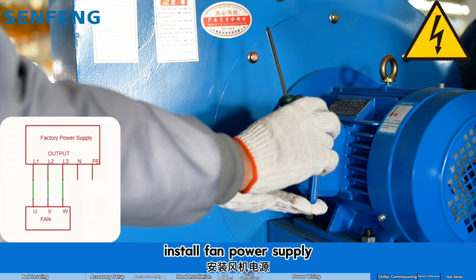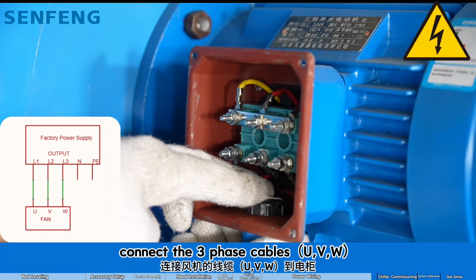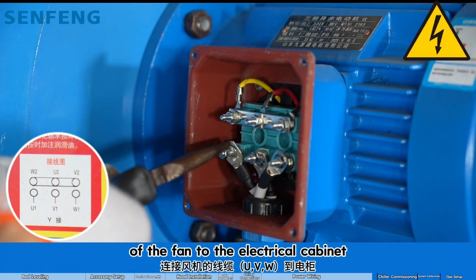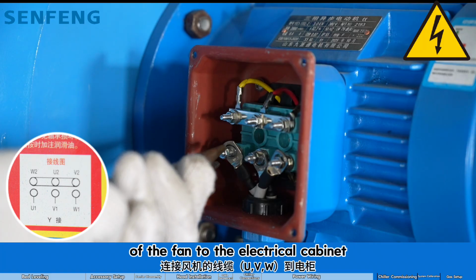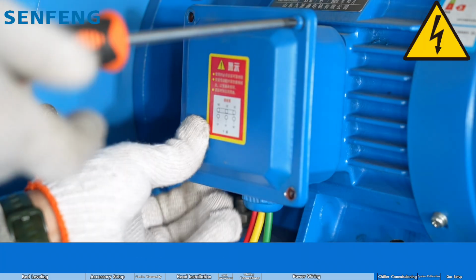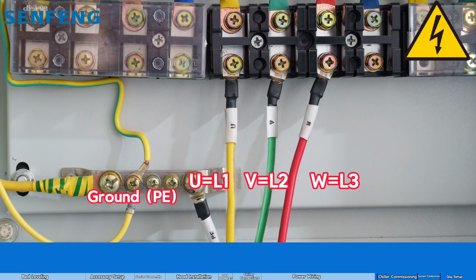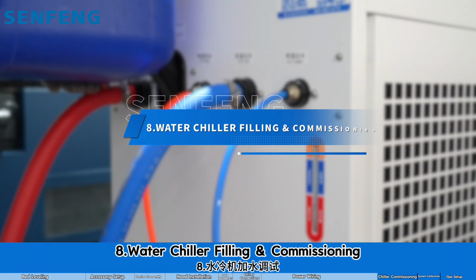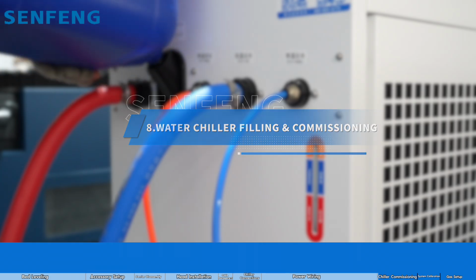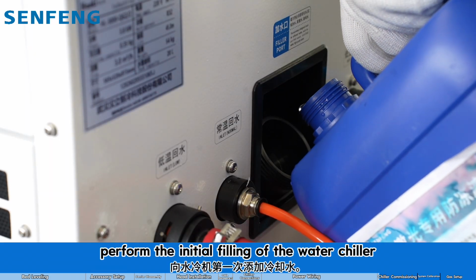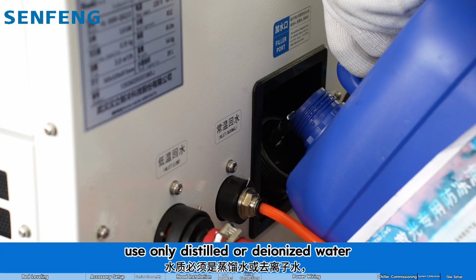Install fan power supply. Connect the 3-phase cables U, V, W of the fan to the electrical cabinet. Step 8: Water chiller, filling and commissioning. Perform the initial filling of the water chiller. Use only distilled or deionized water.